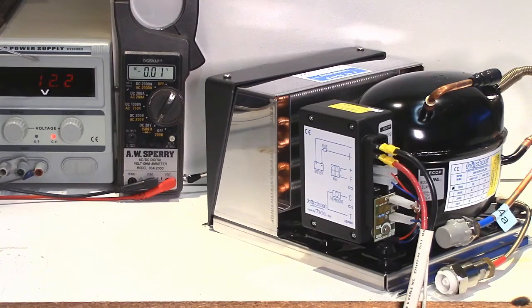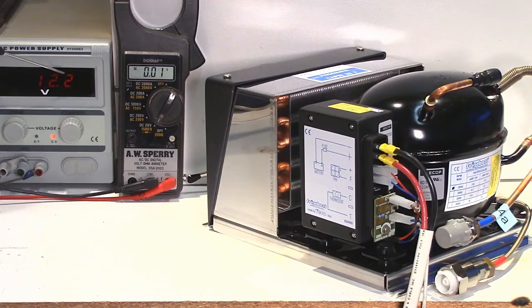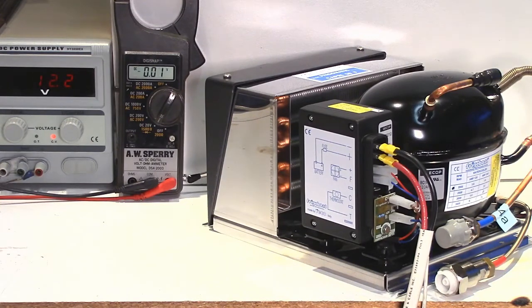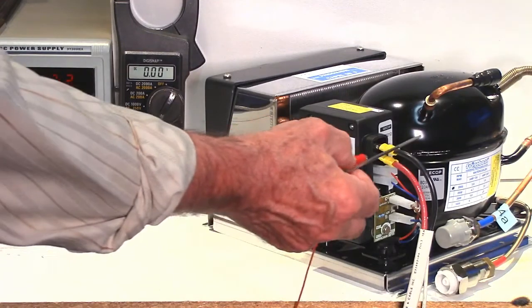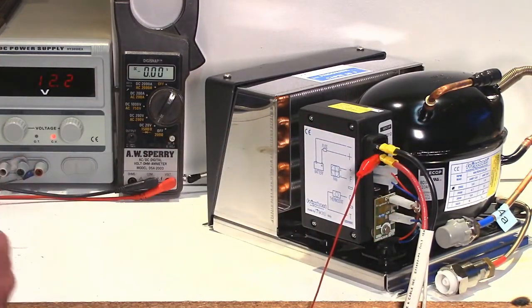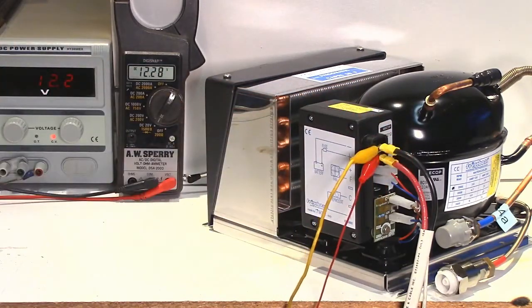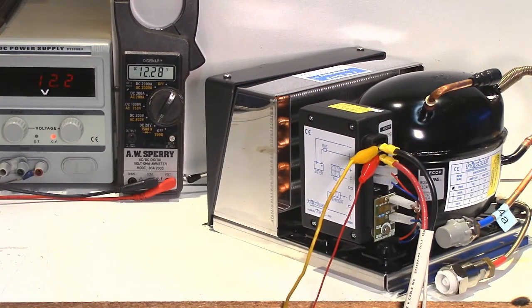We've got a power supply here which is giving out 12.2 volts. Imagine this is the meter on your panel that you're looking at the DC voltage. It's not very bright here but hopefully you can see that 12.2 volts. What we're going to do is hook up another voltmeter and we've got this one here, our multimeter, and put it on to the incoming power so that we can monitor the voltage right at the terminals on the compressor when the compressor tries to start. It's very important that you monitor it at the moment when the compressor tries to start.